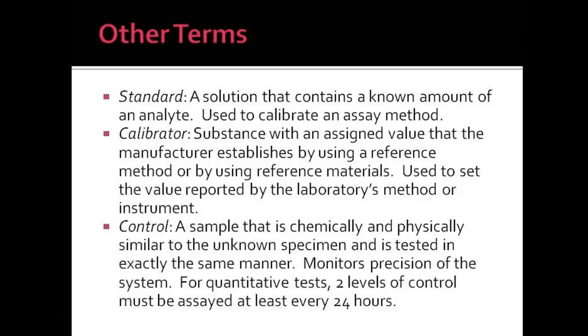A calibrator also has an assigned value, but with a calibrator, we use it to set standards on an analyzer. So we'll tell the analyzer, okay, this is what 100 looks like, this is what 200 looks like. Usually there may be a set of calibrators that we use to set up an analyzer.